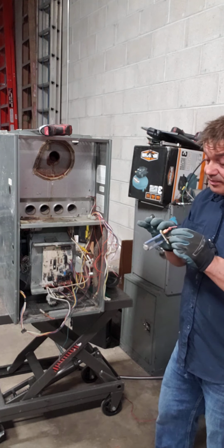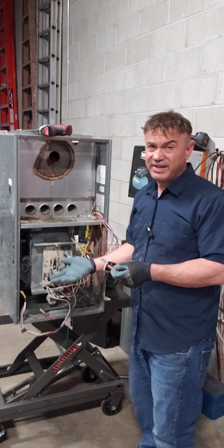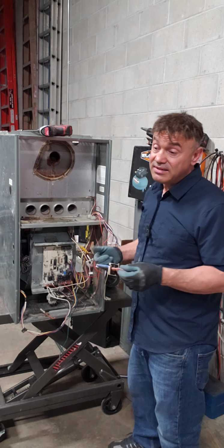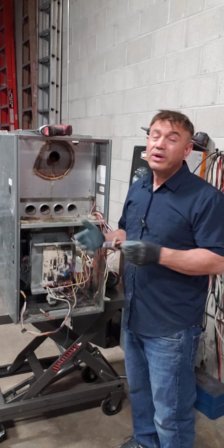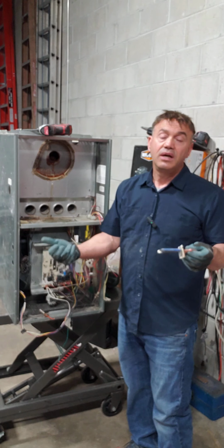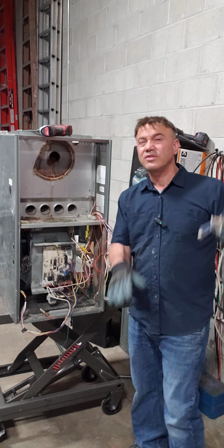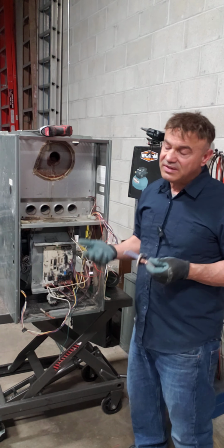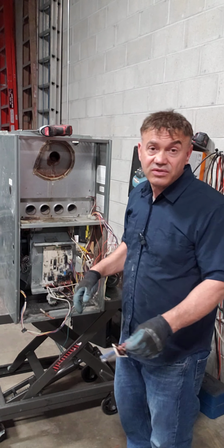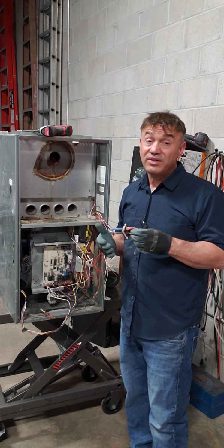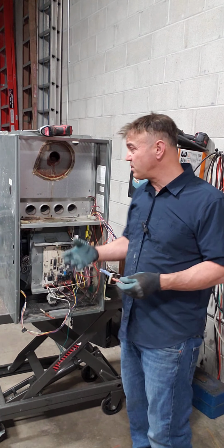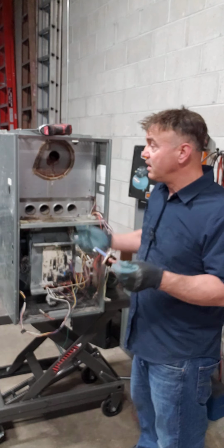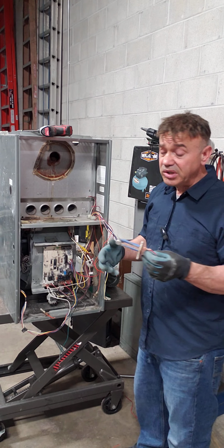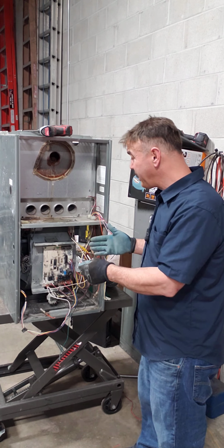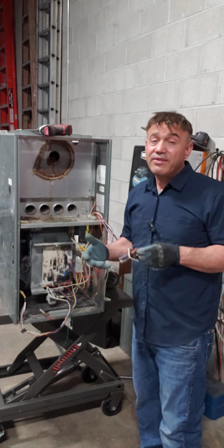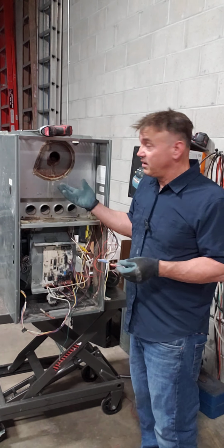So for example, if it's 170, let's say the filter is very dirty. And another thing is, a lot of people, let's say the whole house has like 15 registers, 15 supplies, right? They think, oh, that room is so hot, that room is so hot. Maybe the furnace is too big for the system, for the house, we don't know. So they keep closing these registers. I recommend you don't close more than 50% of the registers. Now they close all these registers and the air starts backing up, right?